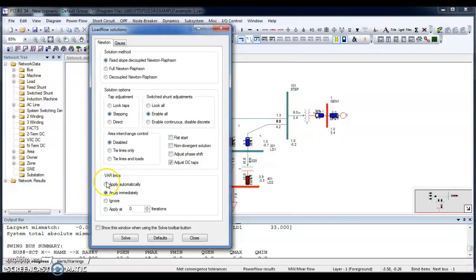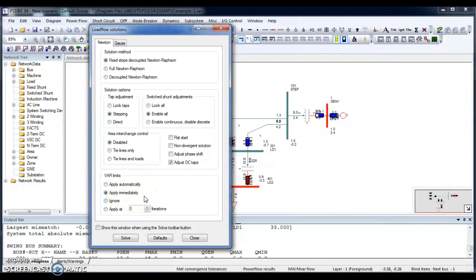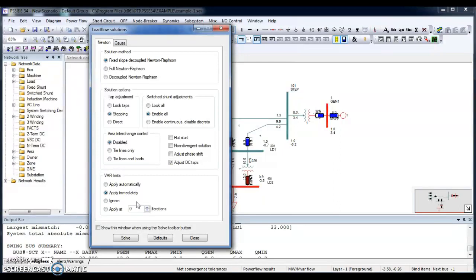So for VAR limits, you can apply automatically, you can apply immediately, you can ignore your VAR limits. Whenever you've got a blown up case, what you usually do is you ignore that VAR limits and track down where you are getting the mismatches. Then you can easily get solved with your network.